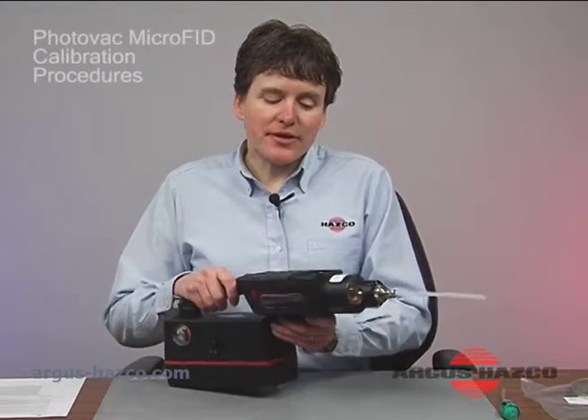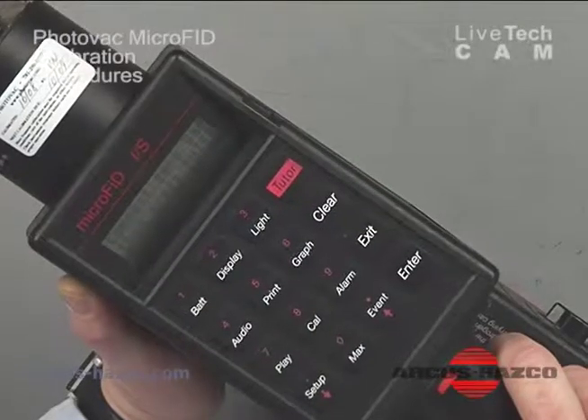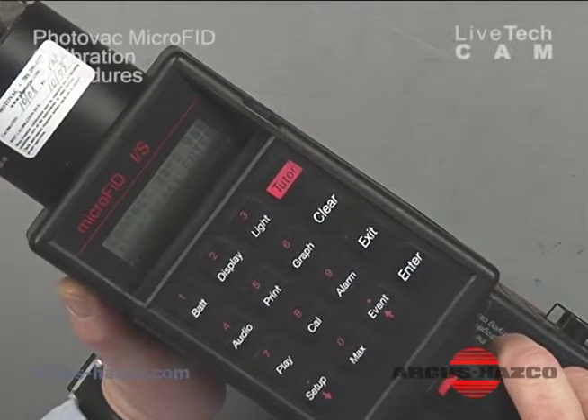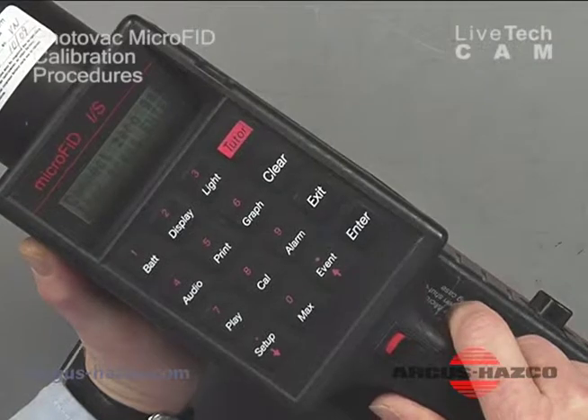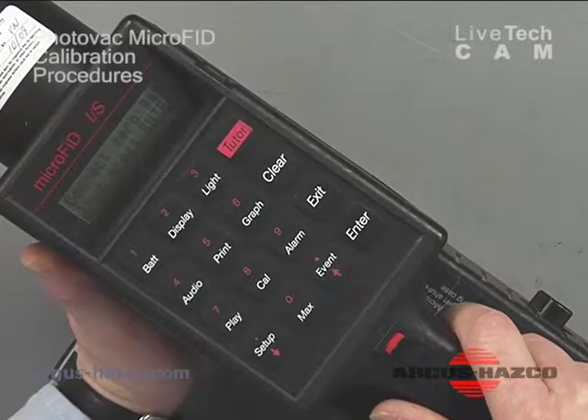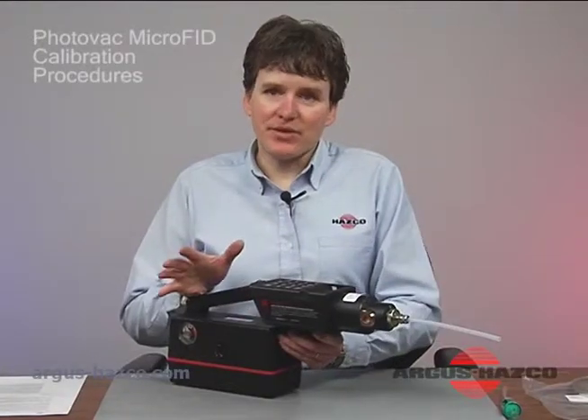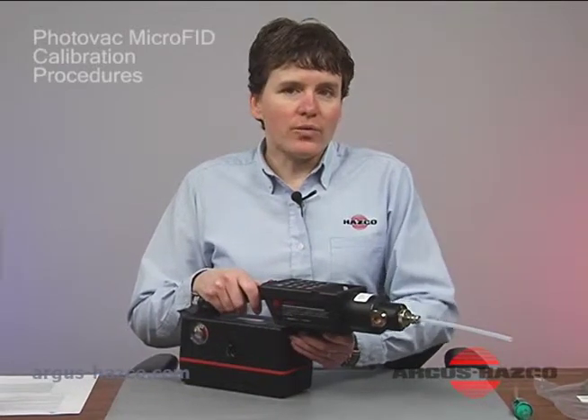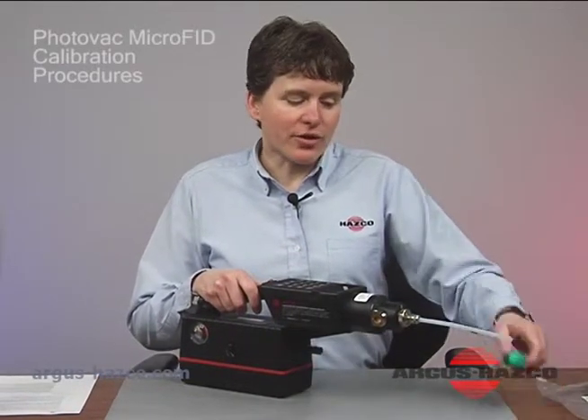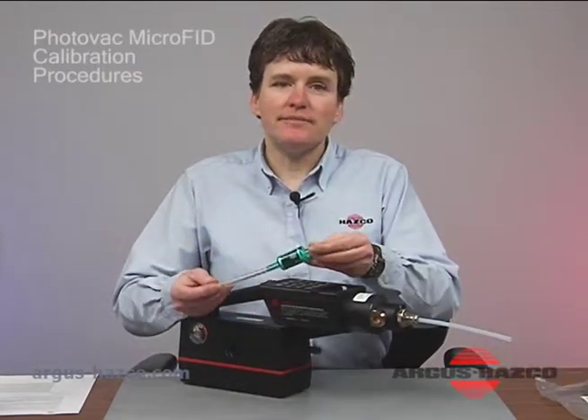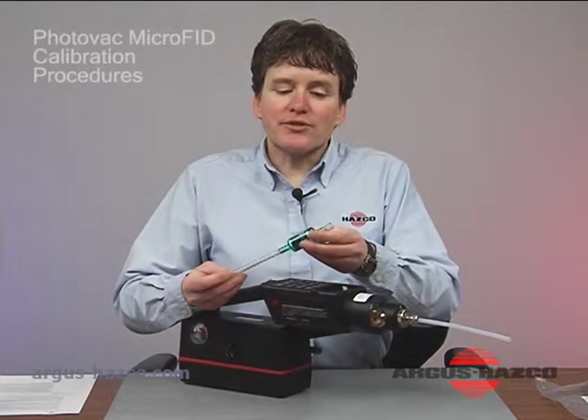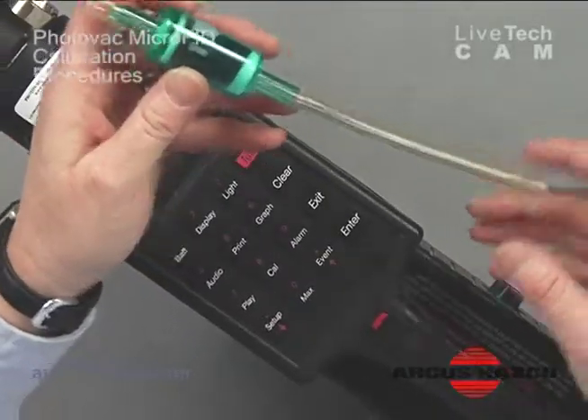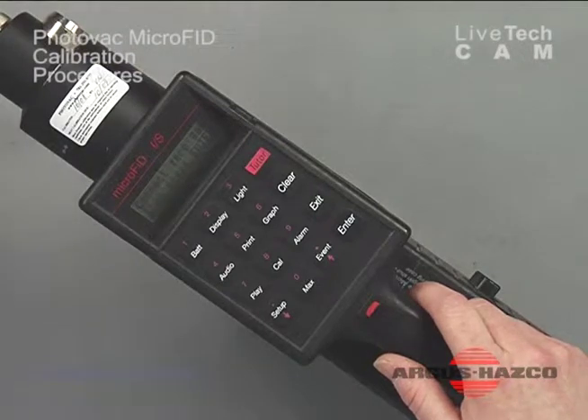Now our next screen here, as you can see, it says connect zero gas, press enter. For our zero gas, you can use a clean atmosphere like we're in now, or you can use the charcoal filter that's supplied with the unit. What this charcoal filter does is it will clean out any impurities in your air except methane or ethane.